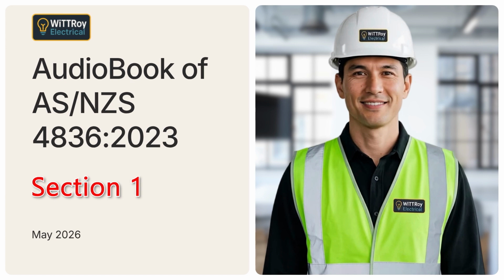Clause 1.4.3 Arc fault. An arc fault is an unwanted electrical discharge through air. In simple terms, electricity jumps across a gap where it should not be jumping. This can create heat, light, sound, pressure, and serious danger to people and equipment. Clause 1.4.4 Arc fault condition. An arc fault condition is a situation where arcs are created because electrical equipment has failed or because a fault has occurred. This condition can lead to arc flash, arc blast, burns, equipment damage, and other serious hazards.